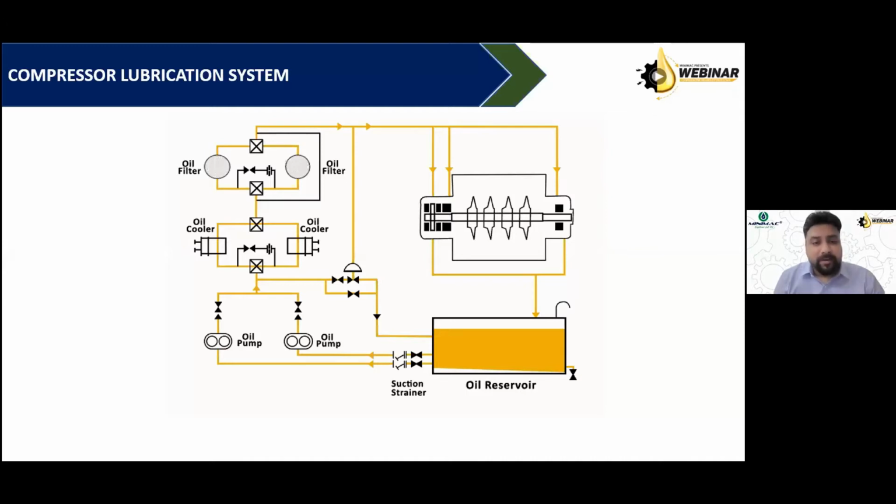So possibly it will be a 25 micron filter element. So will that remove the fine particles? And certainly it won't handle the liquid contamination or the gaseous contamination or the fine sludgy contaminations. And hence, there is always a need for either an oil change in case of compressors or a better purification for the compressor oils.